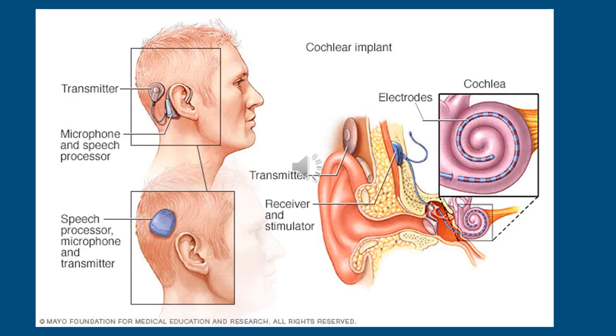So what is a cochlear implant? A cochlear implant is a surgically implanted device placed in the cochlea allowing for electrical stimulation — essentially replacing the hair cells in the cochlear structure that are substantially damaged. You can see in this image that there is an internal device, the actual implant, and also external devices called the processor or transmitter. These external devices contain microphones that pick up sound and allow for communication with the internal implant. With a cochlear implant, the patient is hearing with electrical stimulation, which is very different from a hearing aid, which is considered acoustic hearing.